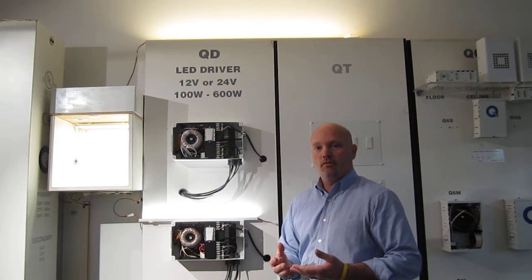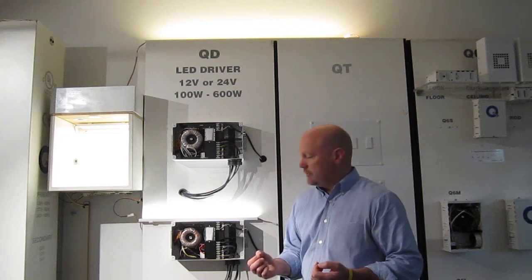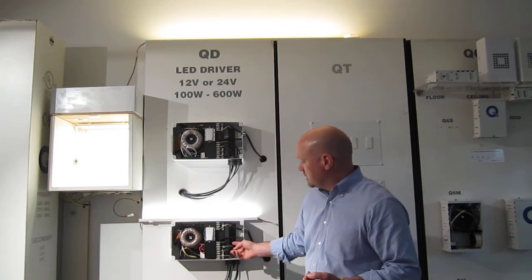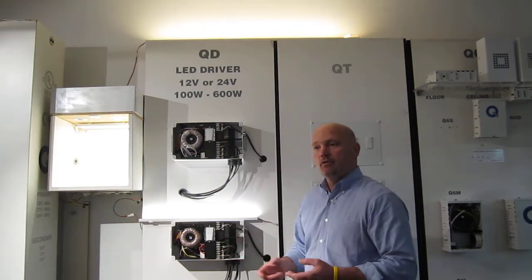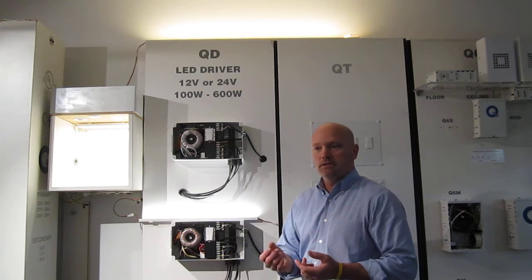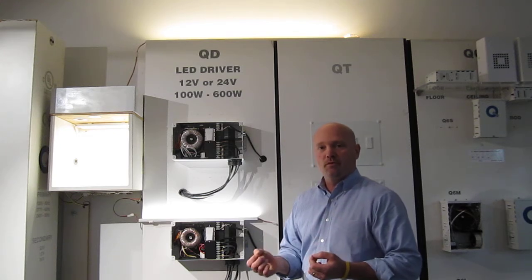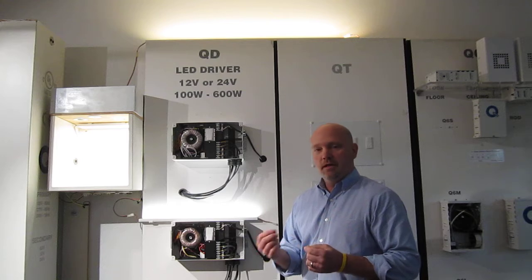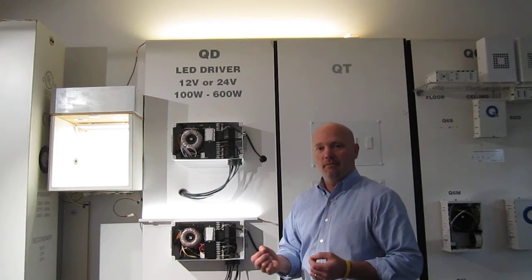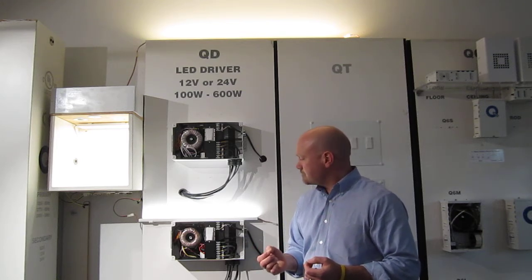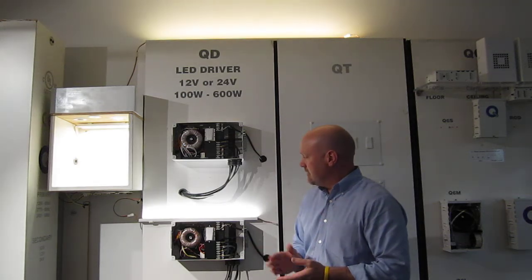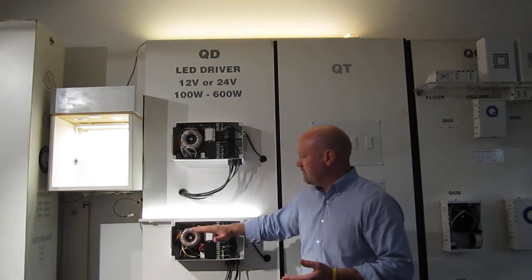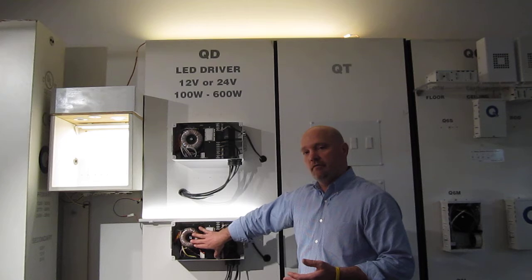We still wire the transformer to Class 2 style outputs. So we put multiple breakers, which you can't really see, but they're back here. Each one of those outputs of 100 watts each is limited to 4 amps at 24 volts, thus meeting the Class 2 requirement for that limitation on the secondary side. The bigger benefit is, instead of the contractor getting those 6 drivers and trying to figure out how to mount them, it's all here self-contained.